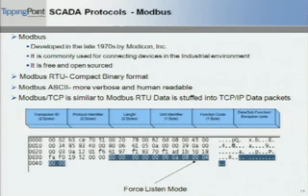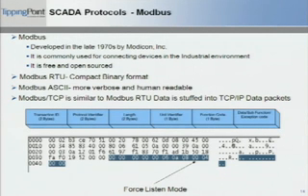Not more than 06. And the next 1 byte is the unit identifier, which uniquely identifies every single node. Like I told you, there can be a maximum of 254 nodes. That's the maximum connection that each RTU can handle. And the next few bytes, the 08 is the diagnostic mode. I will explain that again in the next slides. And the next 2 bytes are the subfunction codes, and the last 2 bytes are the data bytes.